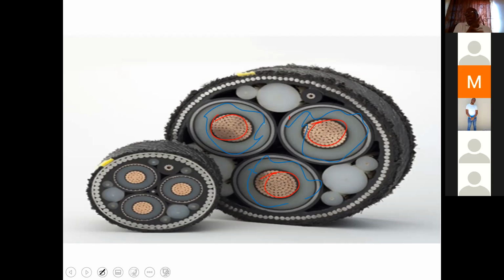So what can we say about the cable relative to the line? For your cable, capacitance is high relative to the inductance. For the line, it's the reverse, higher inductance relative to capacitance. But if we compare capacitance and capacitance for the line and the cable, for the cable it is much higher than for the line. Again, because for the cable we have the charged surfaces in close proximity, separated by super insulators.